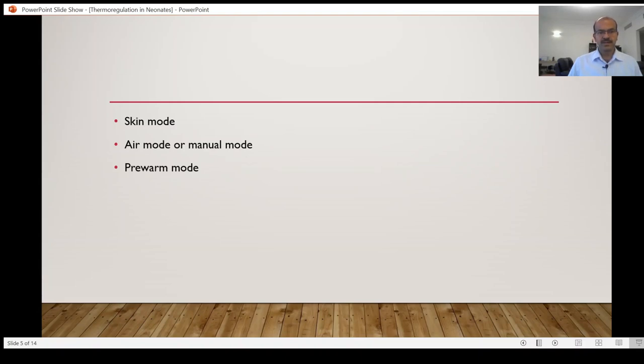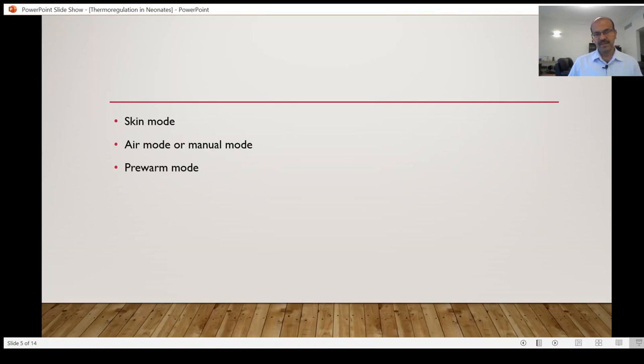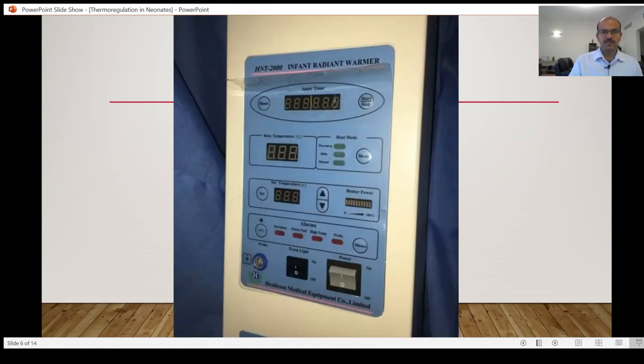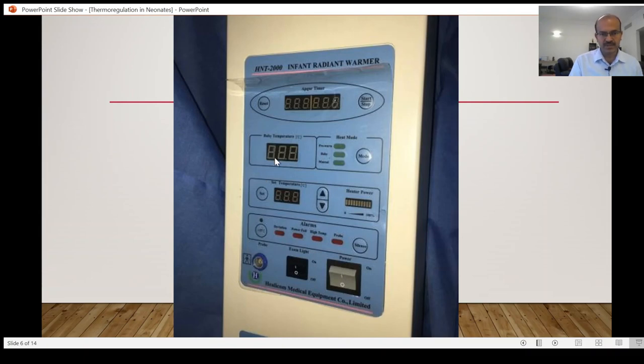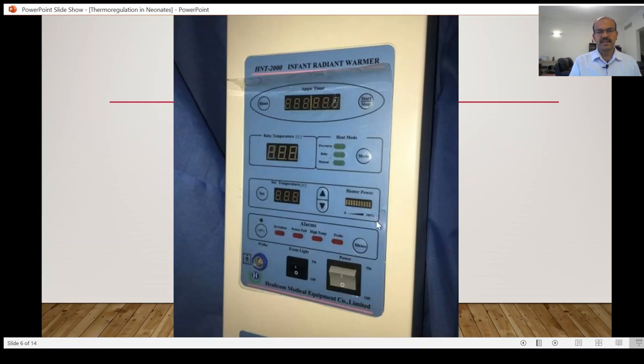If you fix the probe appropriately, the skin mode is handy to adjust the level of heat. Air mode or manual mode is an option as well in the open care system. The main difficulty with the manual mode is that you have to monitor the baby's skin temperature yourself and make adjustments in the heater output.